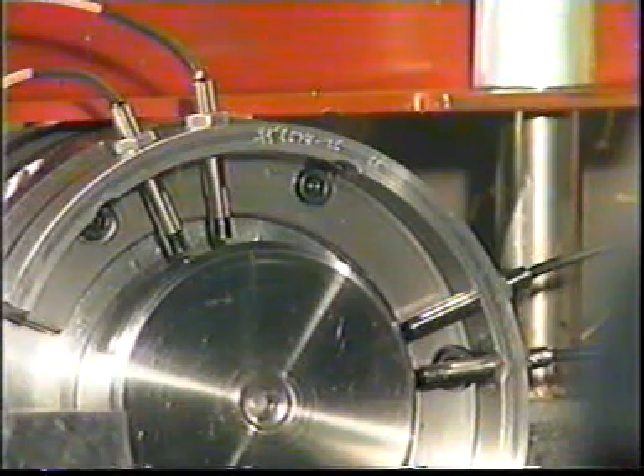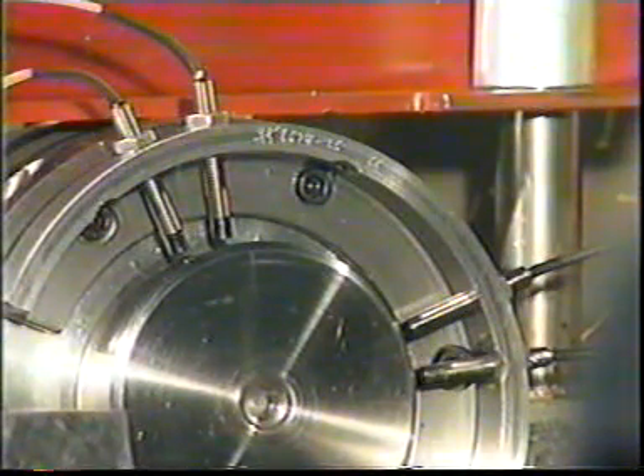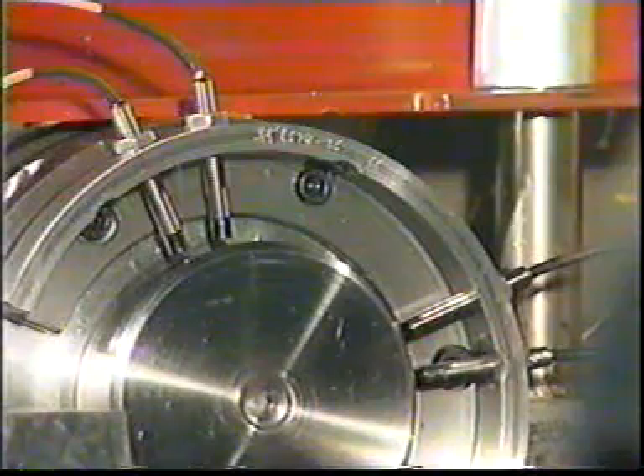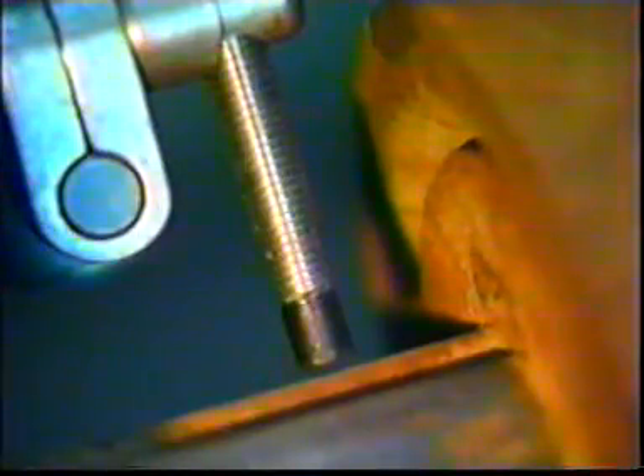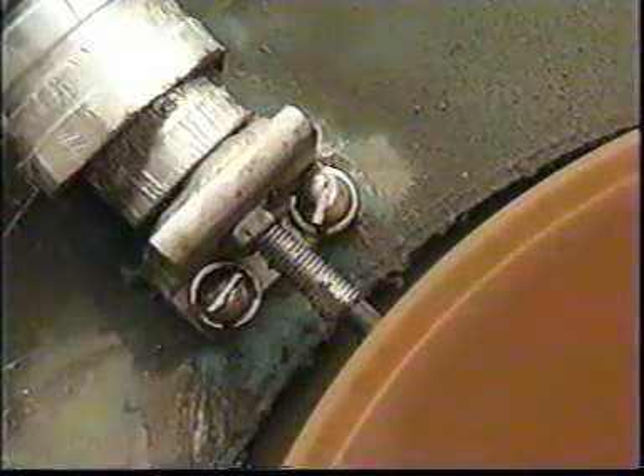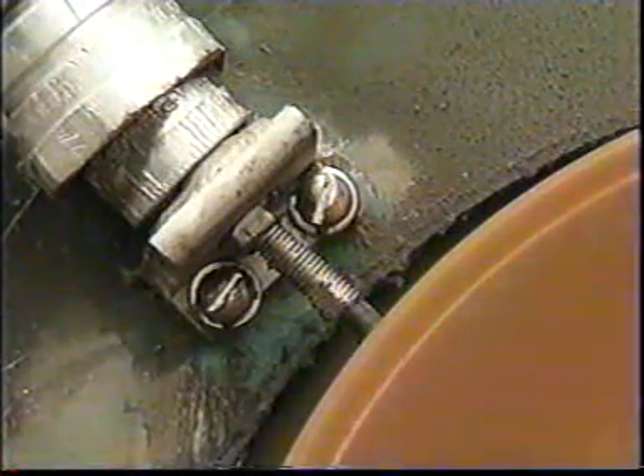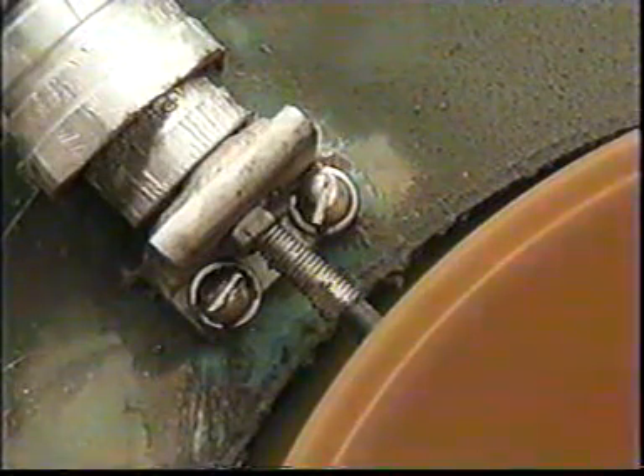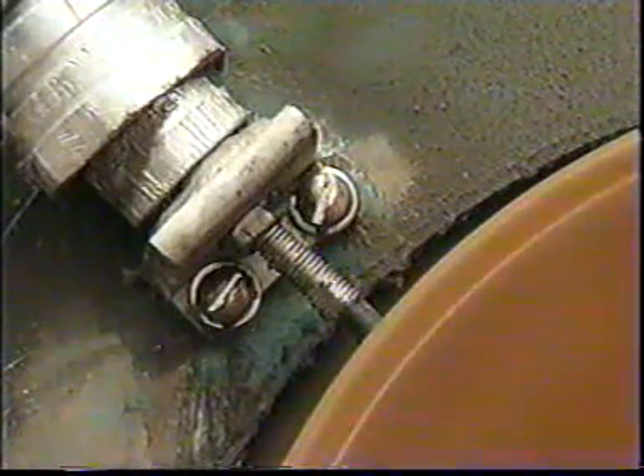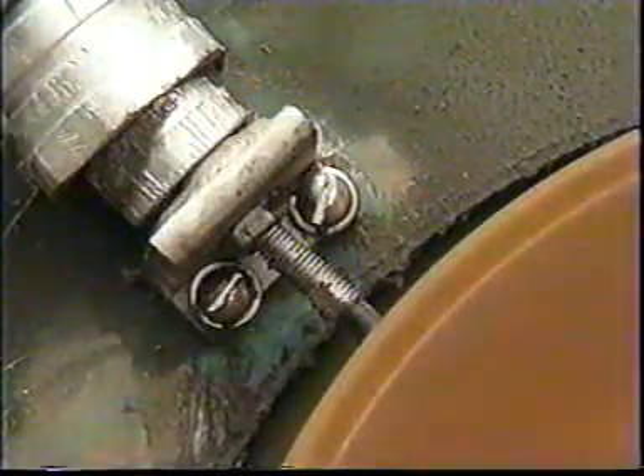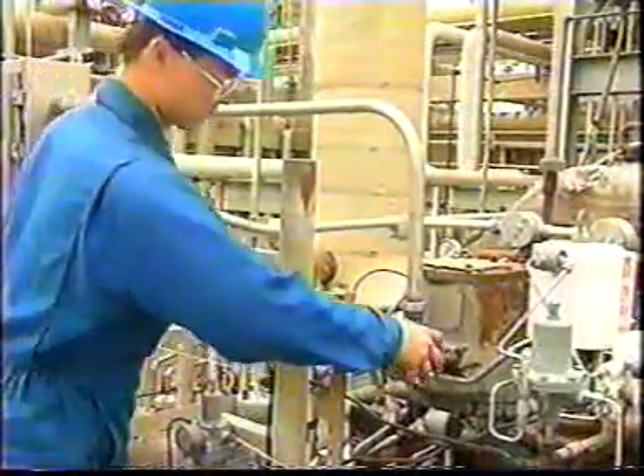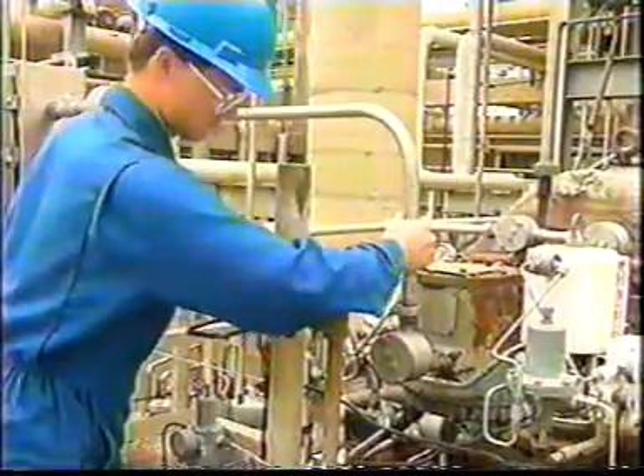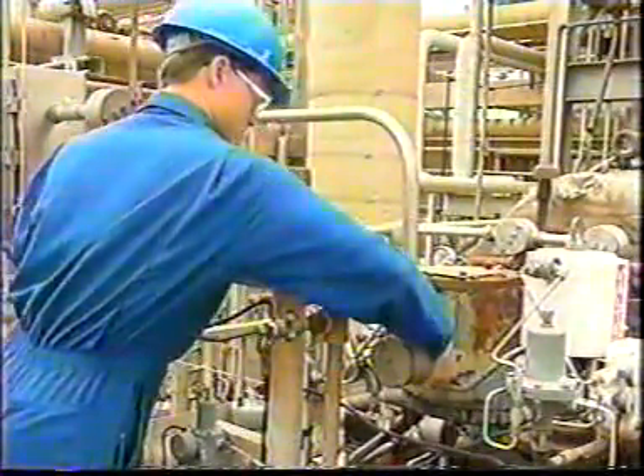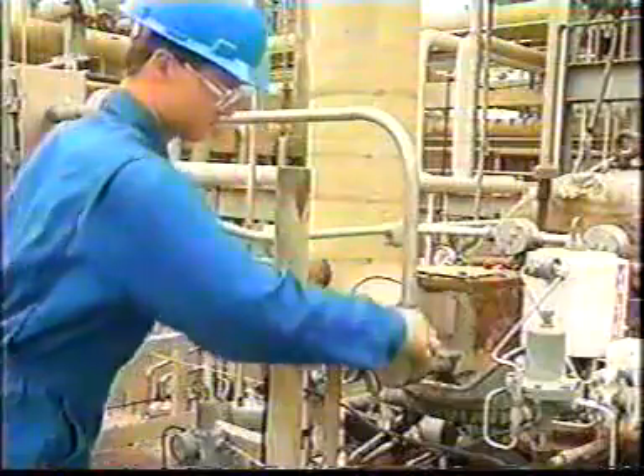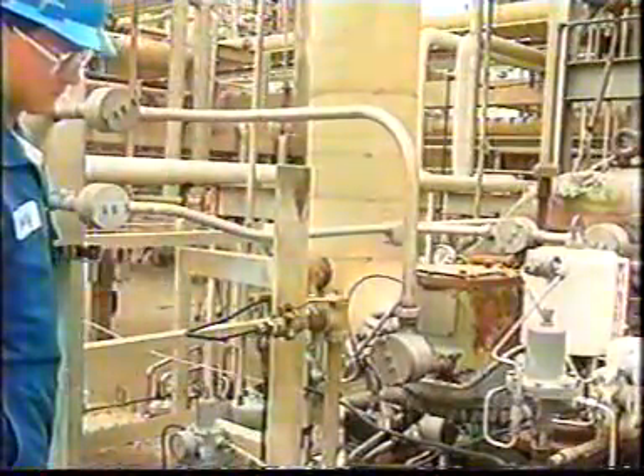Displacement sensors measure motion by measuring the varying gap between the sensor and the sensed element. Proper mounting is important to ensure an accurate and reliable reading. Externally mounted sensors need to be supported to ensure the probe does not vibrate independent of the casing. This means rigid junction boxes and mounting adapters. If the mounting box and mounting adapter are free to move independently, the probe tip will move in relation to the shaft, even if the shaft is stationary.